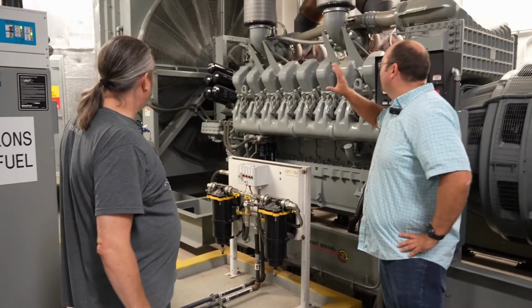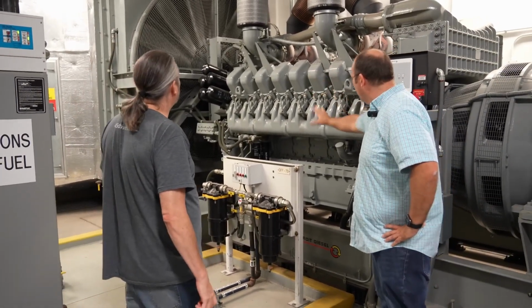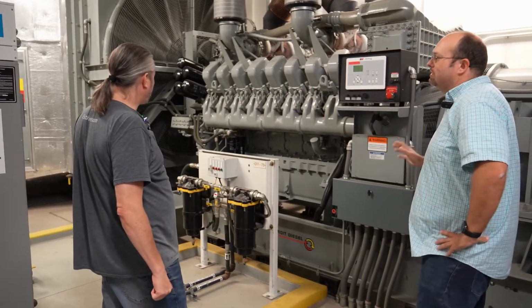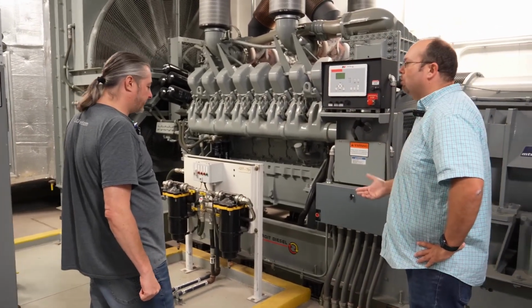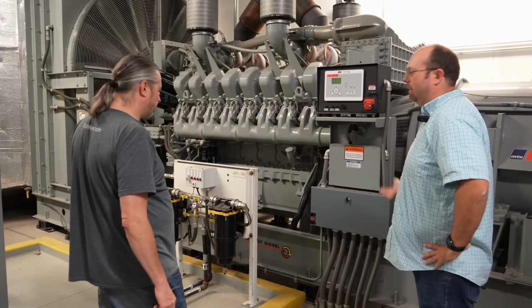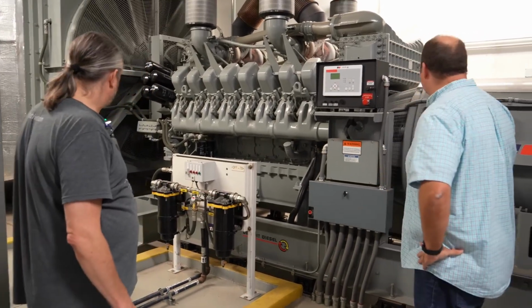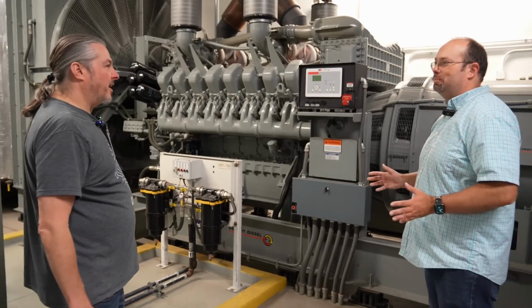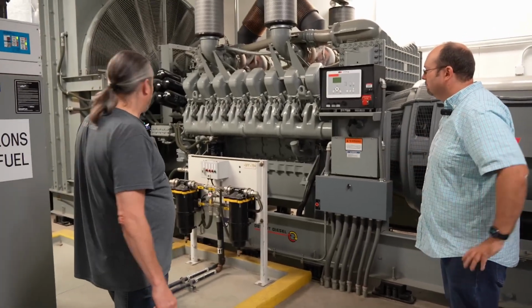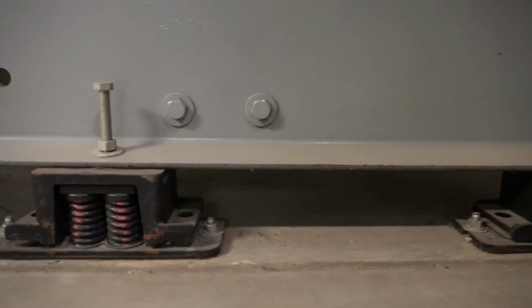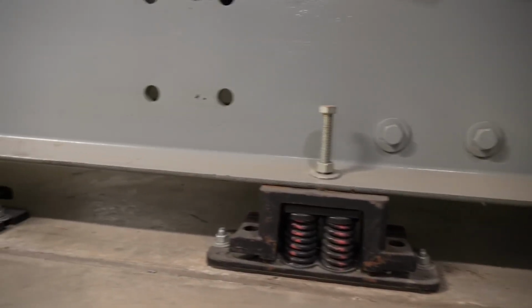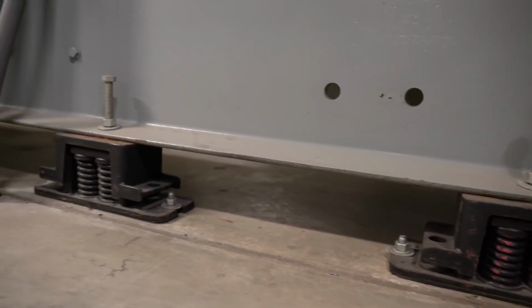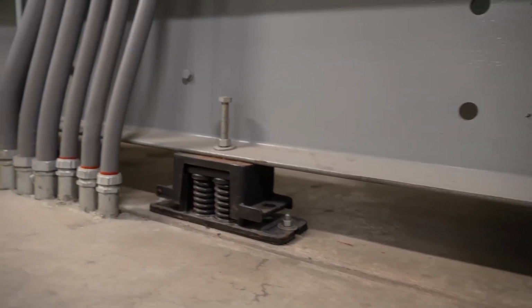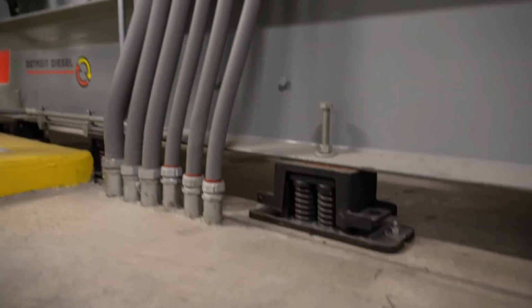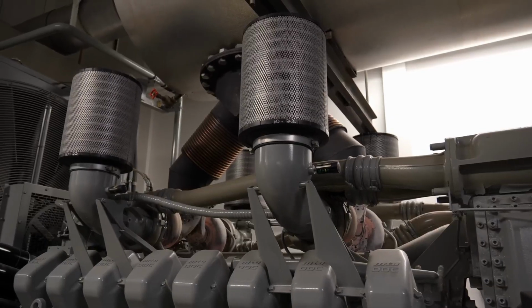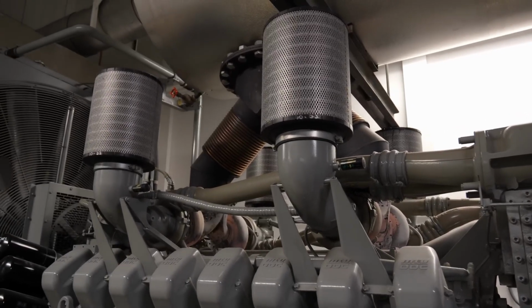You've got redundant filters for the radiator system, oil system. Everything is designed to be easy to service and redundant so that no single component can take this unit offline. That is an absolute massive improvement when you're working on a setup like this. Yeah, and I see all the isolation to keep this from vibrating, because vibration is the enemy of data centers. You got it, 100%. So there's a full suspension tray on these that is load rated, and everything has a little bit of a flex coupling so that it can shift and vibrate without causing any problems.